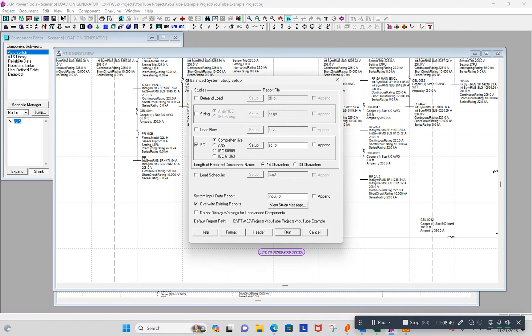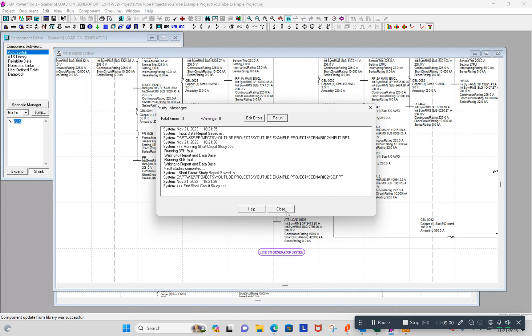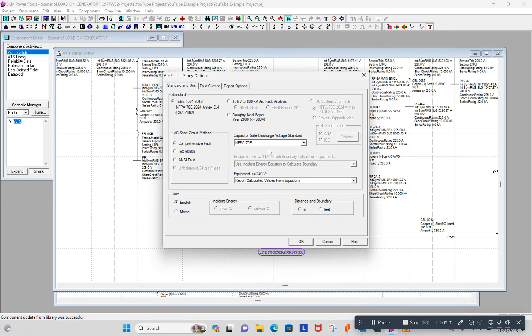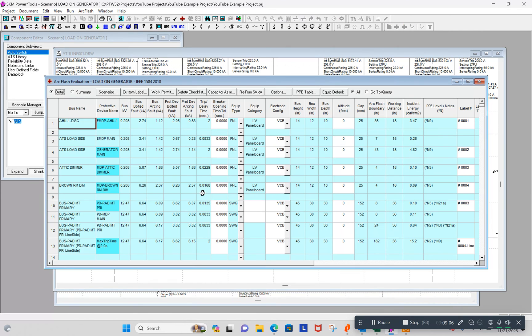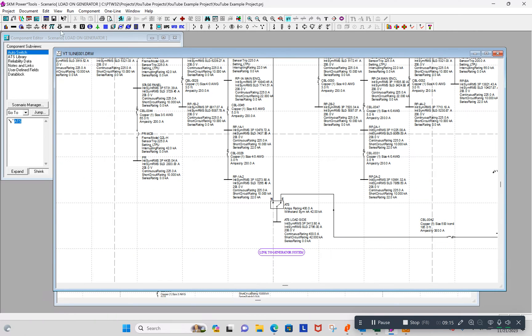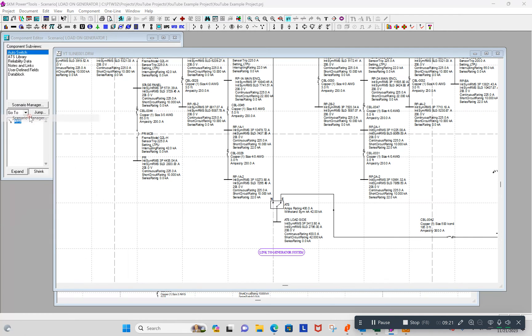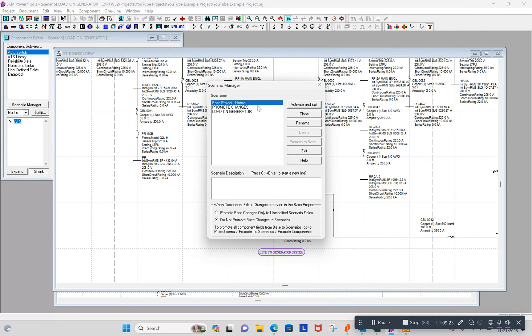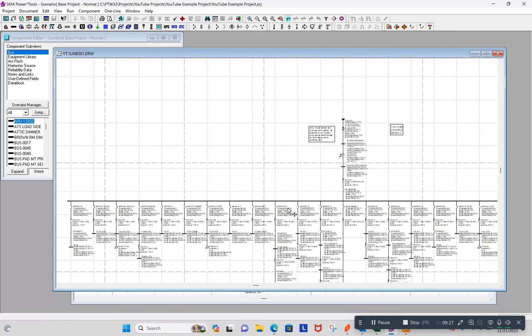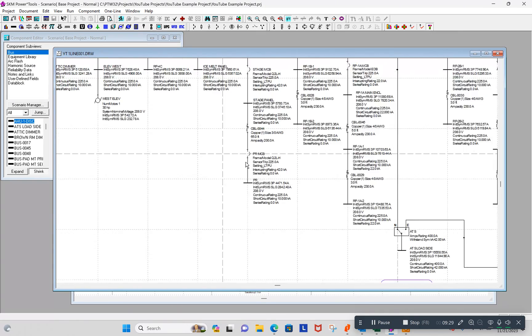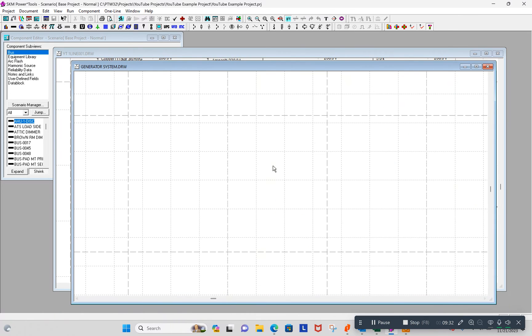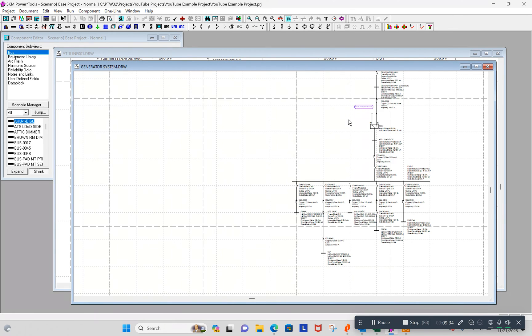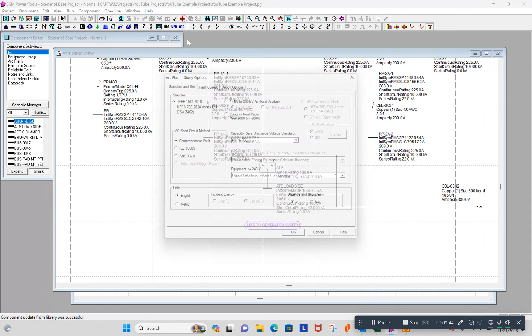So I can run another short circuit study. I don't have any errors. Now everything downstream of this transfer switch just got calculated being fed by the generator. And I can run the arc flash study here or I'll do it again. I'll go back to the base area. But now this just ran everything in the position with the load on the generator. Let's go back to our base scenario. And it should have the transfer switch in the normal position, normal power. And it does. It should be that way here on our other diagram. And it is.